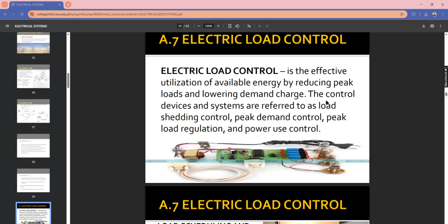Load scheduling and duty cycle controls - installation electric load analyzing and scheduling to restrict demand, shifting large loads off peak hours, and controlling to avoid alteration. And also demand metering alarm - it is a duty cycle control demand, continuously metered, with an alarm set when a predetermined level is exceeded.